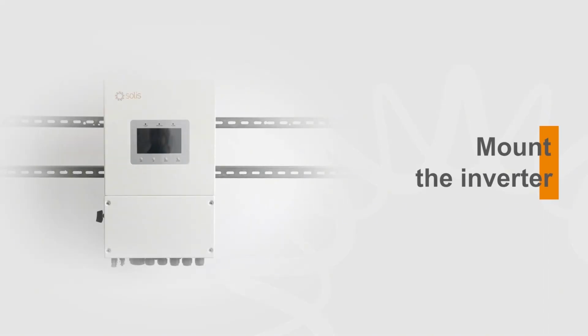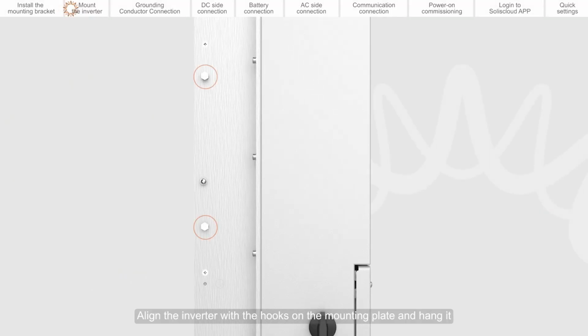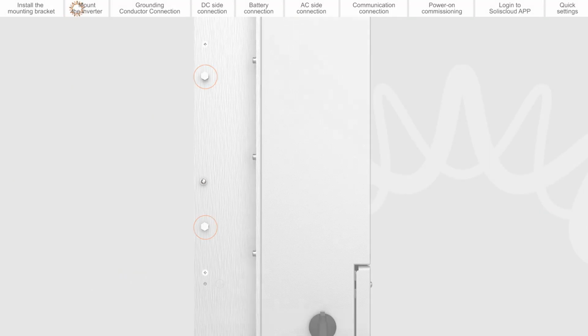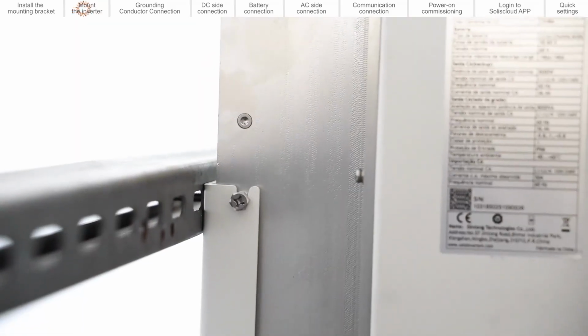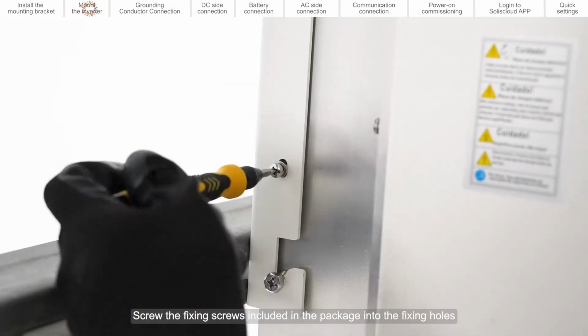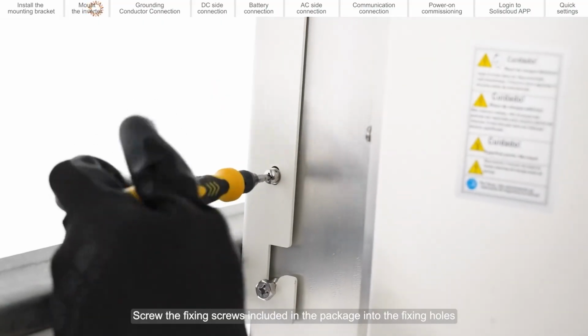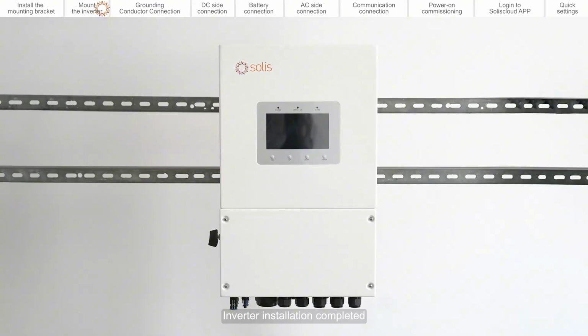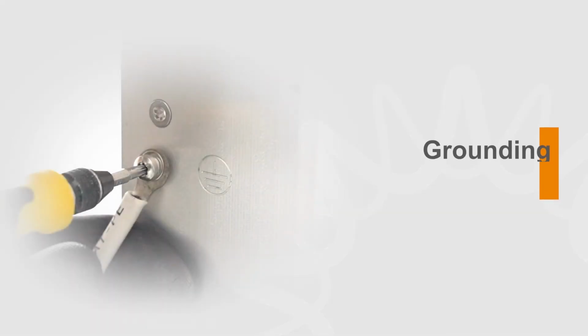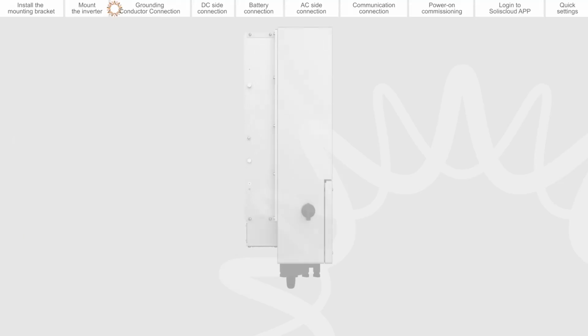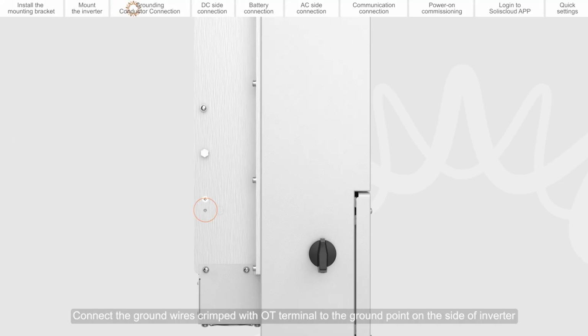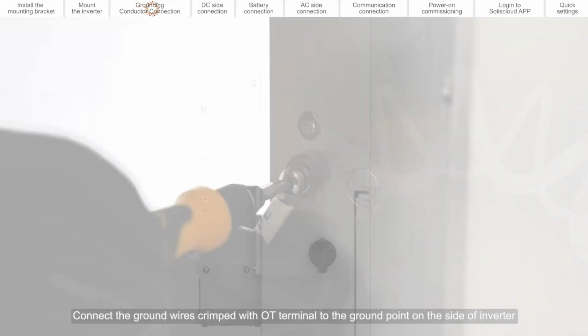Mount the inverter. Align the inverter with the hooks on the mounting plate and hang it. Screw the fixing screws included in the package into the fixing holes. Inverter installation completed. Grounding cable connection. Connect the ground wires crimped with OT terminal to the ground point on the side of inverter.